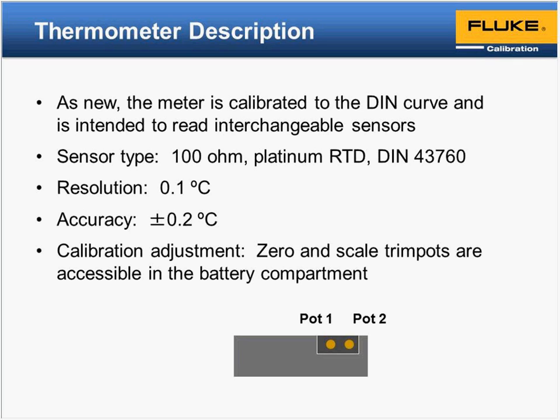Typically, in our scenario, as new, the meter was calibrated and it will conform to the DIN curve. In our example, it's a readout and a PRT, so we're going to work with a probe that's a 100 ohm platinum. For this example, we could call it DIN class A, DIN class B, but we want to keep in mind we're working with a 100 ohm probe. The resolution on our readout is going to be 0.1, and the accuracy is plus or minus 0.2. We've got to rate or scale the unit. In our example, we're going to pretend that we've got trim pots on the back, one for the low, one for the high: trim pot 1, trim pot 2. That's simulating what we used to do here live on one of our sensors. That's where we pick up on this example.